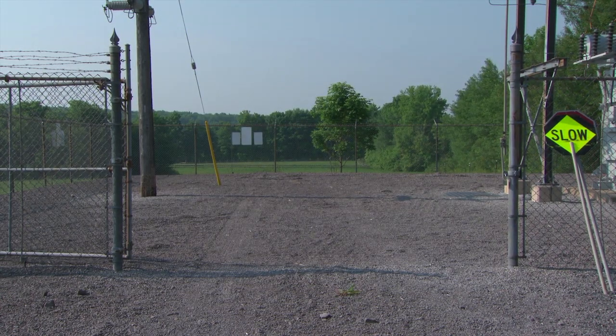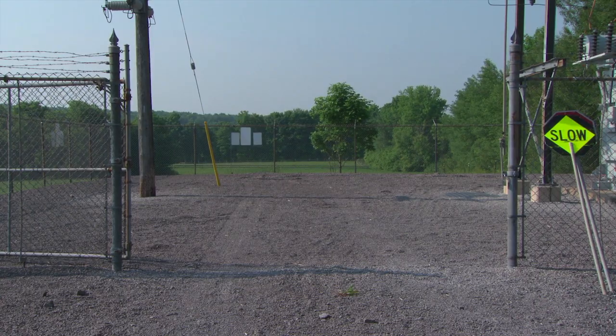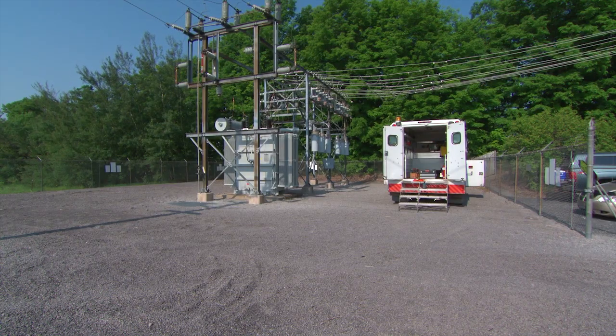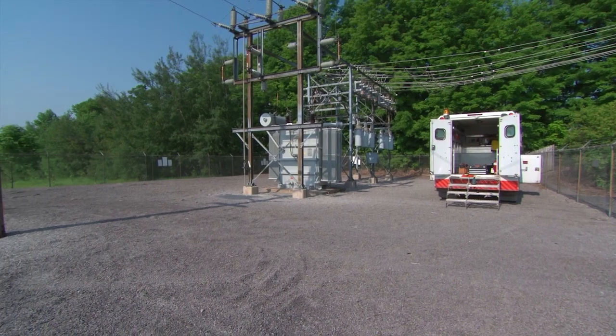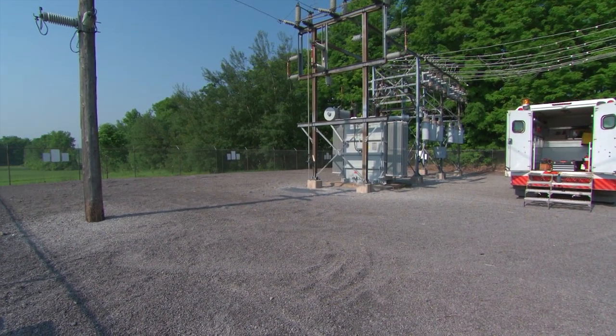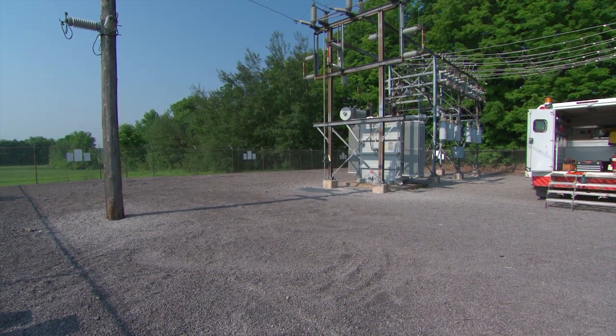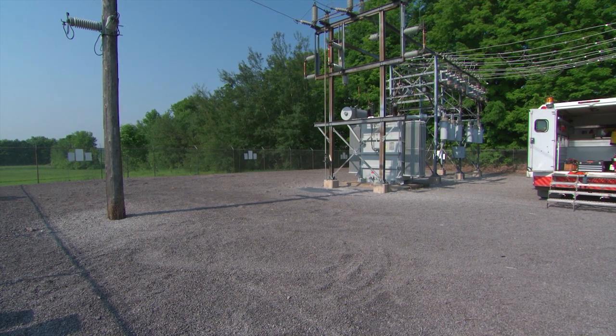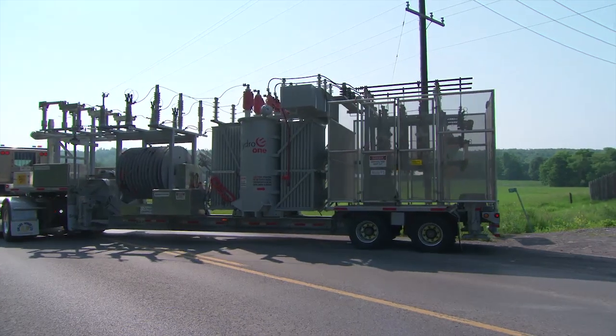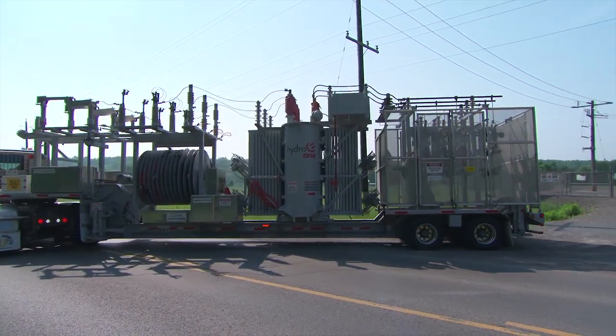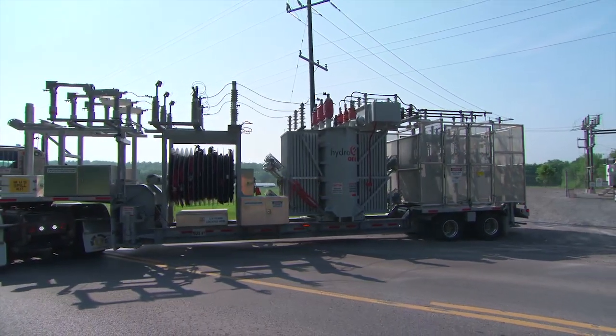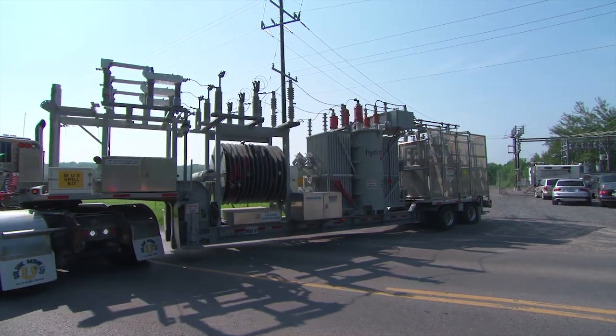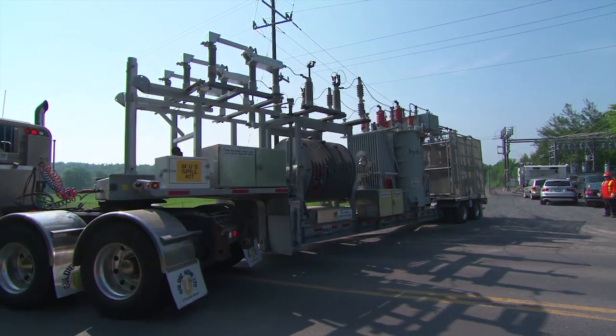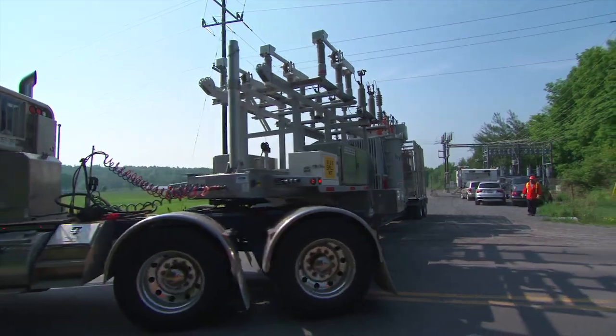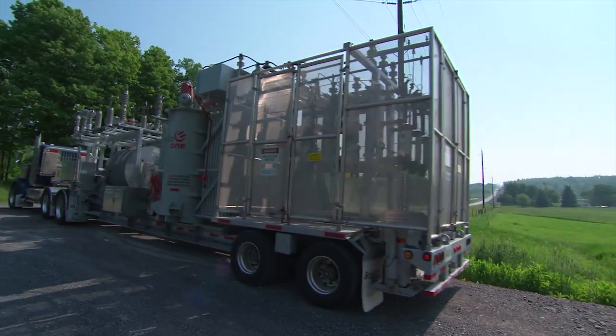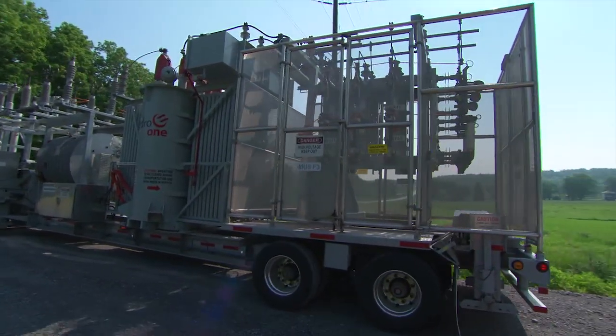Before the MUS arrives, complete a site visit to determine the proper location to land the MUS. The location must allow for proper high-voltage phasing connections and low-voltage feeder connections, limits of approach adherence, proper clearance for required work on the DS equipment, necessary grounding connections, 2.5 meters on either side of the high voltage end of the MUS to permit extensions of the two outside phases, and a minimum of 3 meters between the MUS and the station perimeter fence.